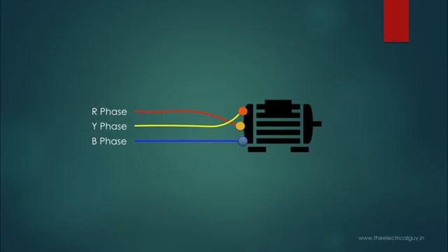Why is phase sequence important for induction motors? Because the direction of rotation of the motor can be changed with a change in phase sequence. So if your motor is running in the opposite direction, phase sequence could be one of the causes. If your three-phase load is purely resistive, then a change in phase sequence will not affect anything. But it may affect unbalanced inductive or capacitive loads.